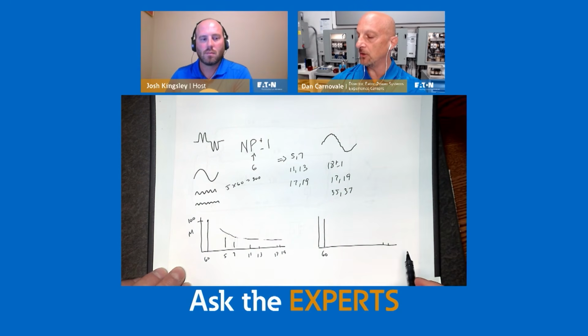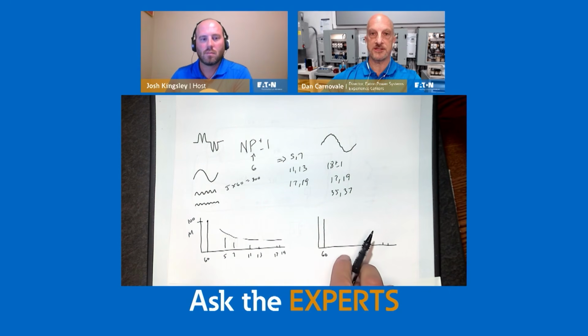That's why we look at certain applications and say, at some point, I might want to go with an 18 pulse drive because, even though it might cost a little bit more out of the gate, I might not have to deal with the harmonics after the fact. So we look at where I can take advantage of higher pulse numbers and so forth. And I can do that within the individual drive itself, or using phase shifting transformers as an example.